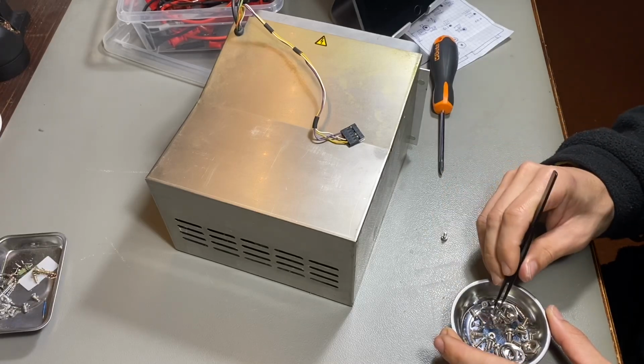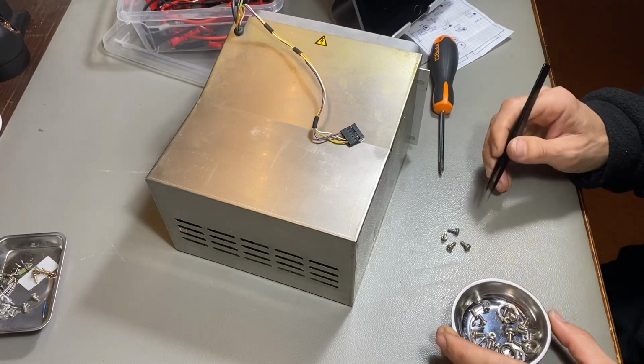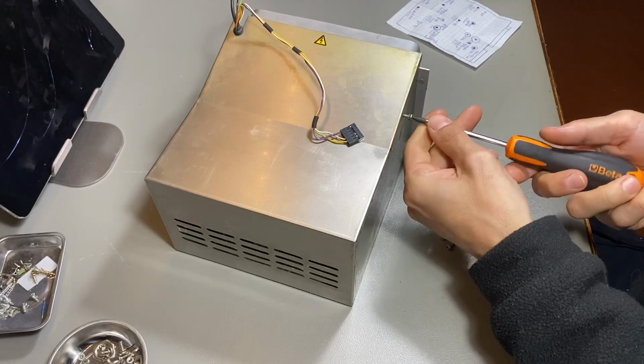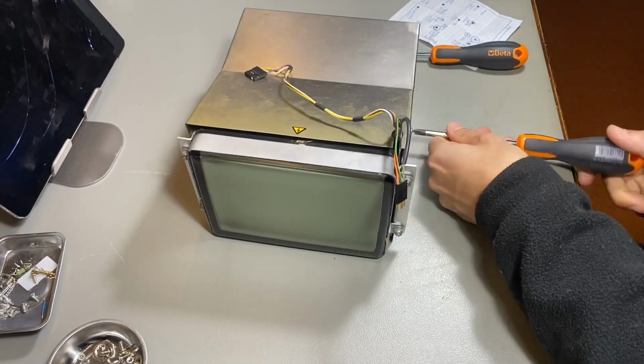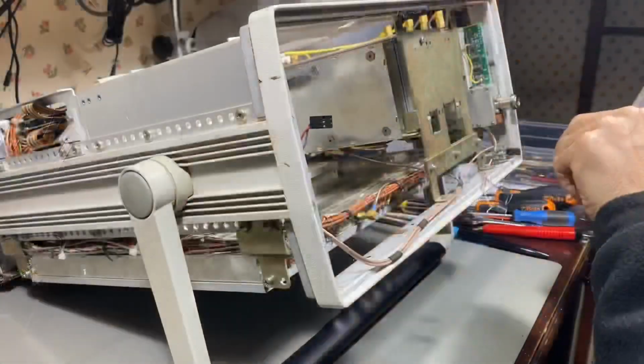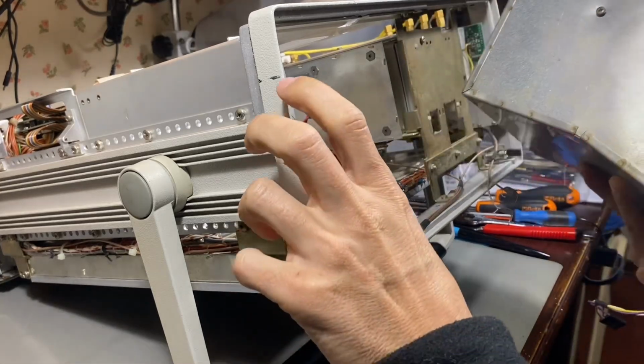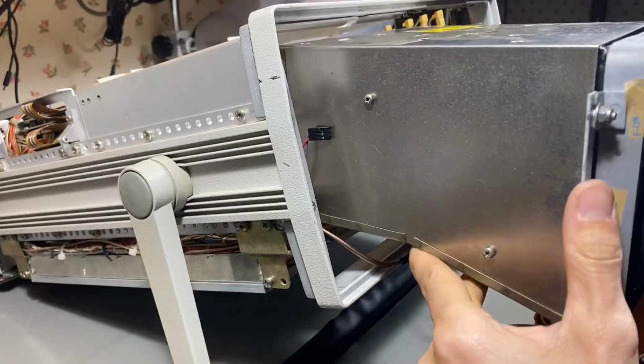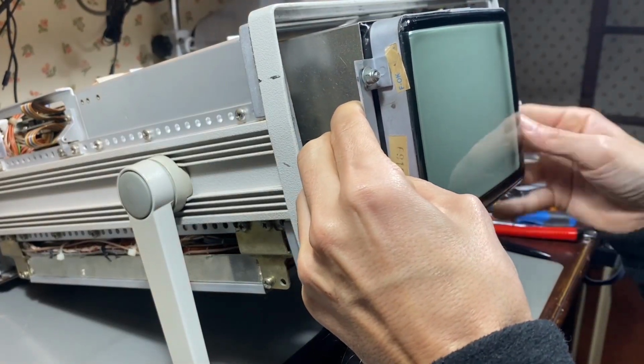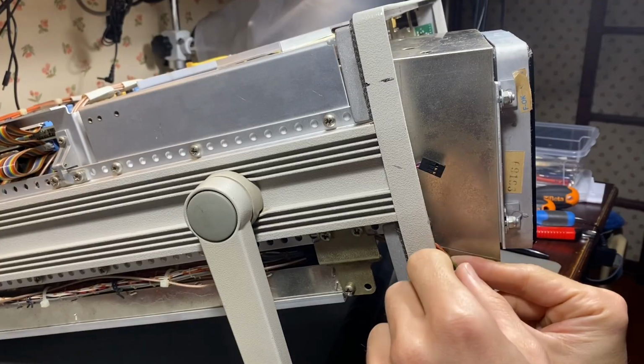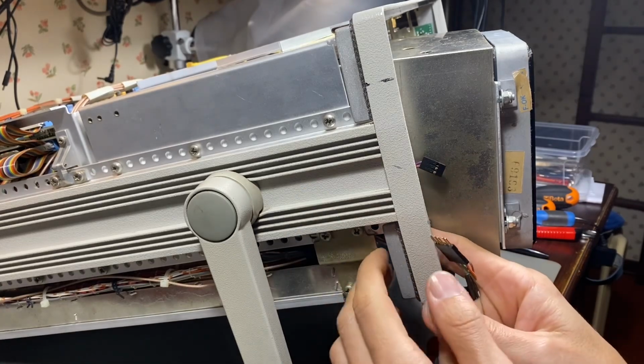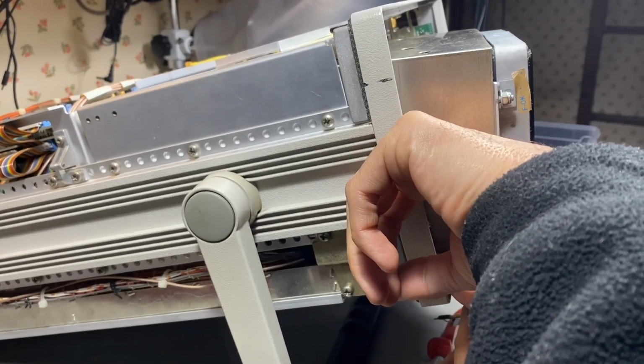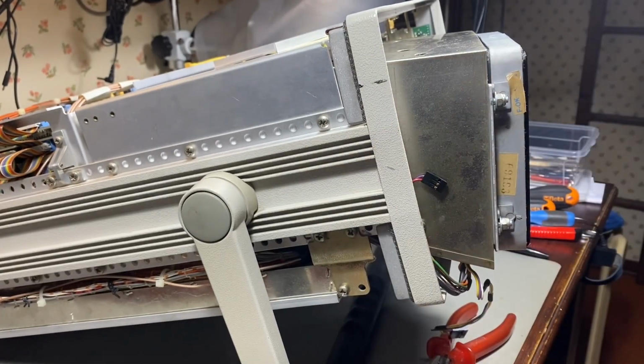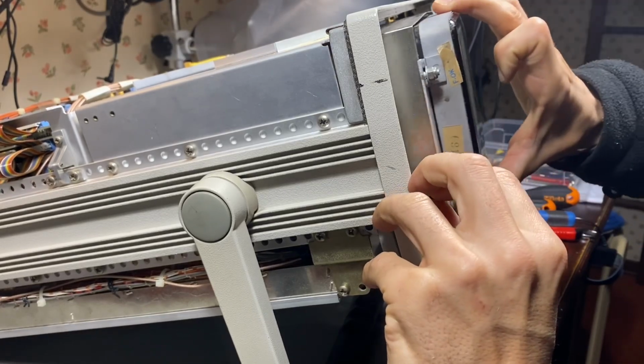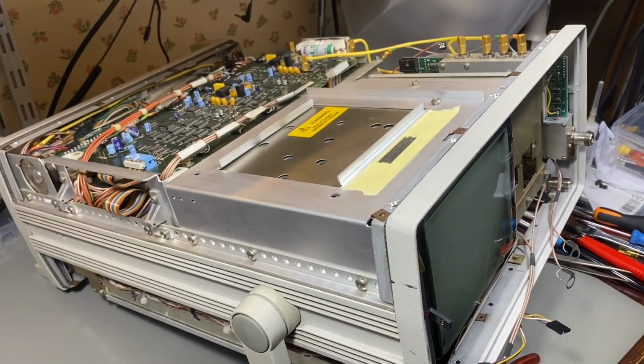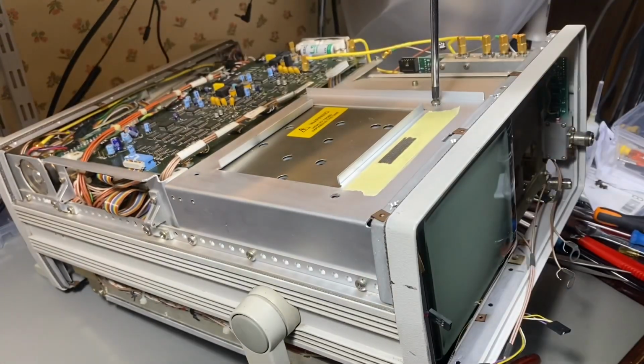Okay, now I put the screws back in. It's 4 in total, 2 on each side. Put the entire module back into the instrument. To do that, I remind you to pay attention to the cables and the two connectors on the left side. This is the one bringing the CRT signals and power from the power supply distribution, from the back basically. And it's tough to connect. And the small one is going to be connected when we put the front panel back in.